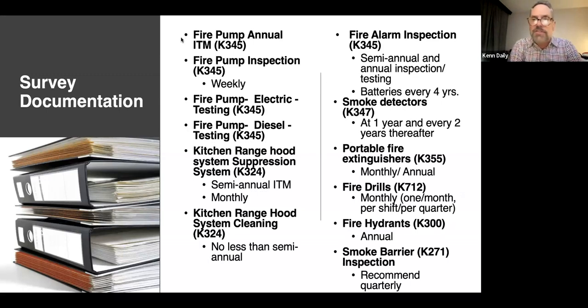Electric is monthly, diesel is weekly. And then you have an annual fire pump inspection, testing, and maintenance done by, again, a company would come and do that fire pump inspection, testing, and maintenance. So there's a fair amount of oversight of fire pumps.